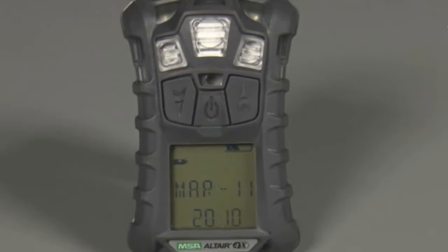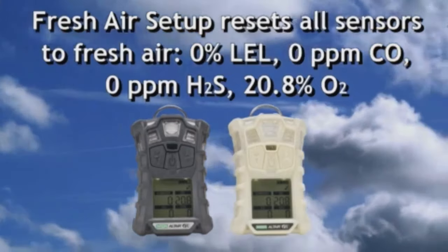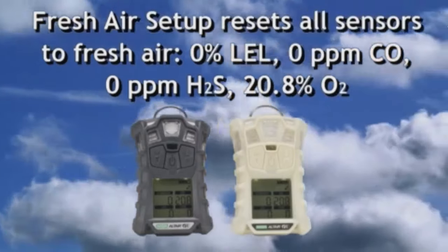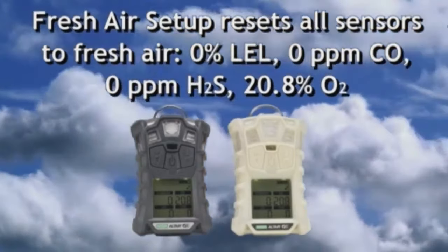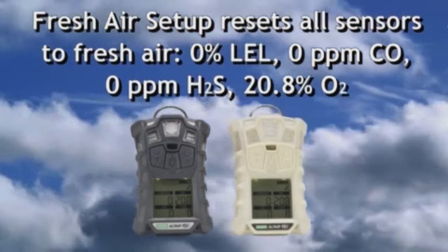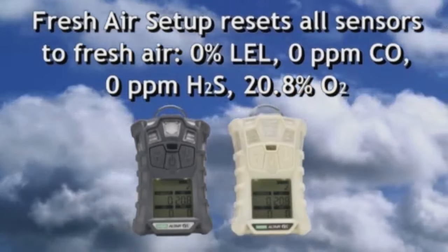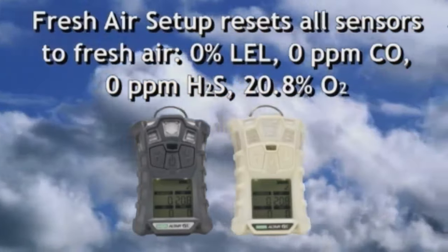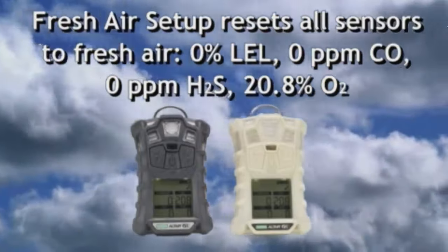if feature is activated. The last startup sequence page alternates between FAS and current gas readings as a prompt, asking users if fresh air setup should be performed. This page is optional and can be turned off through MSA Link software. Fresh air setup allows users to reset all sensors to fresh air values: 0% LEL, 0 ppm carbon monoxide, 0 ppm hydrogen sulfide, and 20.8% oxygen.